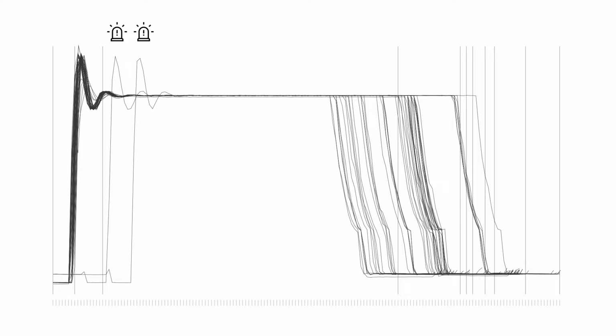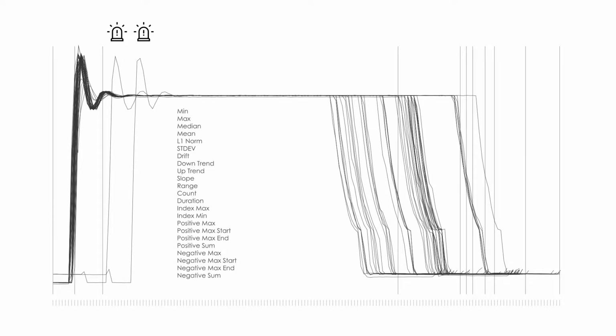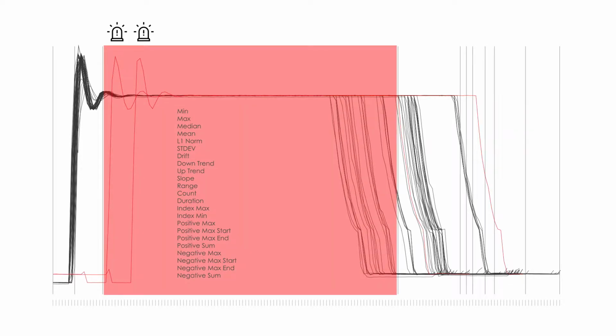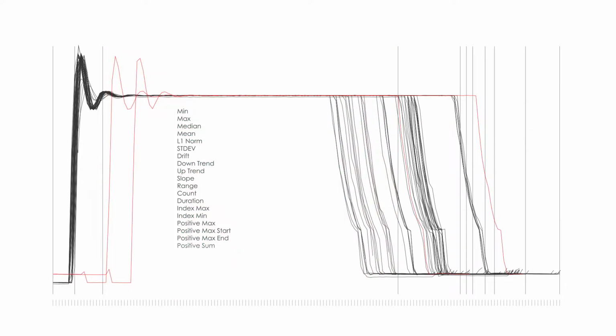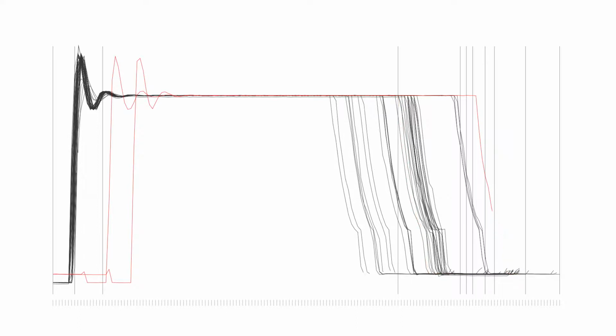DFD, or Dynamic Fault Detection, analyzes the trace data pattern of the wafers from one or more lots within a module with 23 algorithms and scores every wafer pattern. If one of the scores exceeds the limit, DFD detects a fault. The chart highlights the recipe step where a fault occurred. For deeper analysis and insight into the fault, DFD provides trace data chart by the parameter and the wafer.